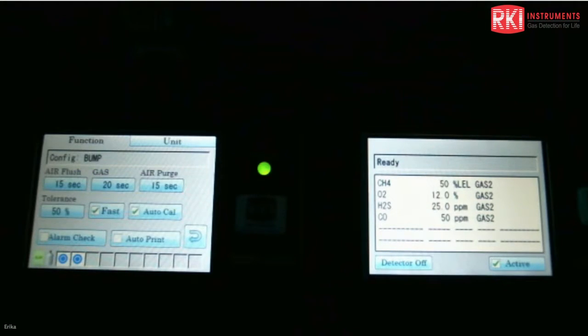I'm going to go through the bump first. Once you click that, it's going to show times for air, gas, and air purge. Tolerance is also there. There's a little thing here that says fast. It's a fast bump, and it just means that if you run a bump test and within the first 10 seconds it goes within 50% tolerance or whatever you have set for your tolerance, it's going to pass that bump test, so it saves you gas.